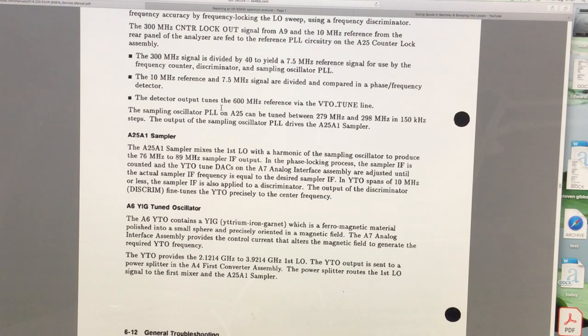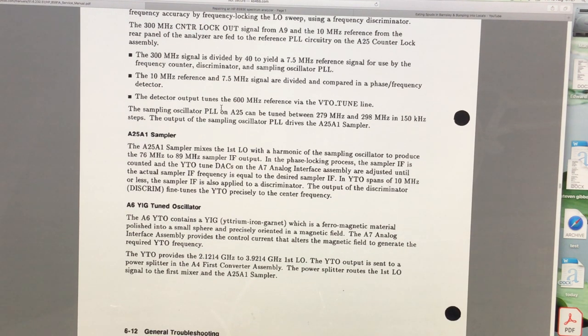300 MHz counter lock out signal from A9 and the 10 MHz reference from the rear panel of the analyzer are fed to the reference PLL circuitry on the A25 counter lock assembly. The 300 MHz signal is divided by 40 to yield a 7.5 MHz reference signal for use by the frequency counter, discriminator and sampling oscillator.